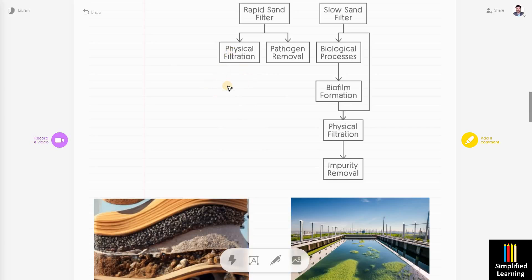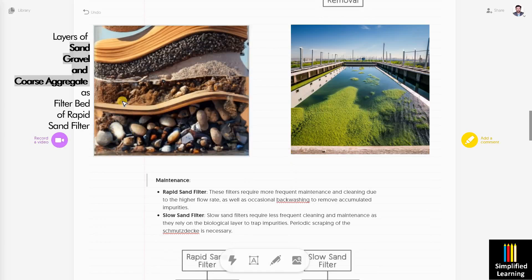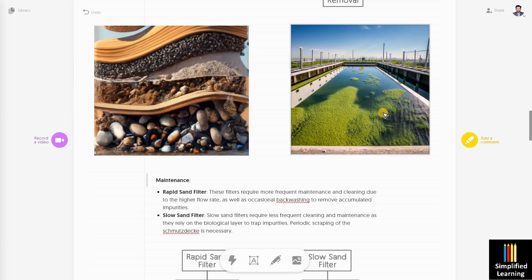In rapid sand filter, physical filtration and pathogen removal take place. In slow sand filter, biological process — that is biofilm filtration — and physical filtration together cause impurities to be removed. You can see the media layer arrangement in the rapid sand filter diagram, and on the right, the biofilm that has been formed. In slow sand filter, biofilm growth is continuous, and after continuous growth, head loss occurs — meaning water can no longer pass through — and then it is time for scraping and renewal of the biofilm and filter beds.